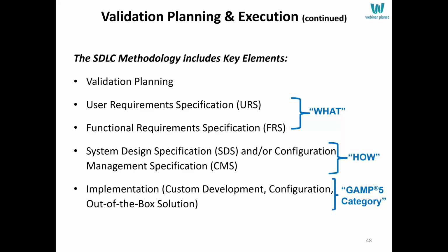Back in 1983, most code was homegrown. Most of it was developed by an IT group on site. And so these documents were usually available. But with the advent of using a lot of vendor packages, cloud providers, software as a service, you don't always get these documents. And it's not important, because really, once you install the application software package and you show through validation testing that it meets all the requirements and the intended use, and this is done on a risk-based approach, that automatically confirms the underlying design and configuration are appropriate. If they weren't appropriate, the system application wouldn't work right.